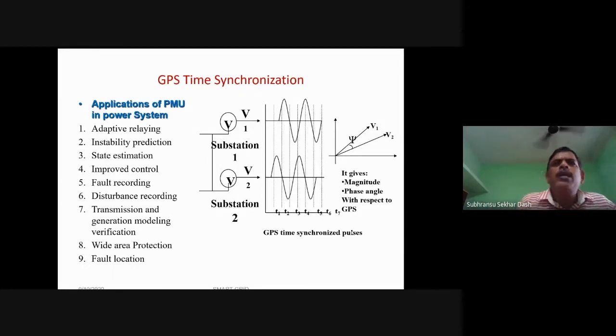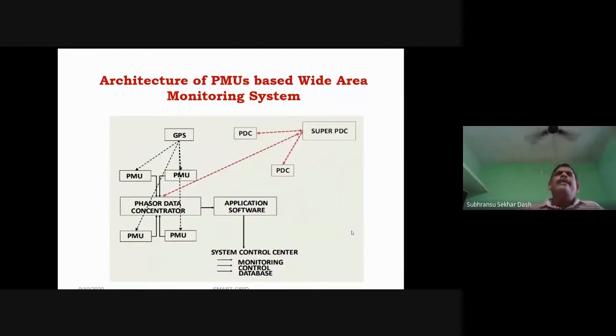So, as you can see here, voltage and currents are measured at each substation. So there will be a phase difference between substation 1 and 2. These are GPS synchronized, which gives magnitude and phase angle. This is actually a PMU based wide area monitoring system. So you have PMUs in different areas, at different substations, that can be monitored by wide area monitoring systems. You understand? The data should be monitored so that you can find out whether the system is stable or unstable.